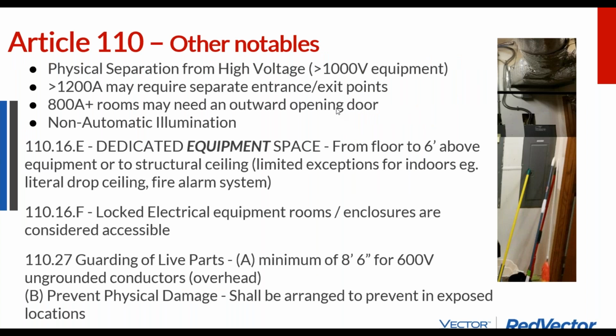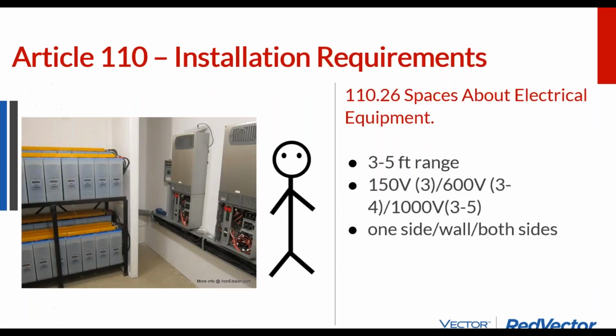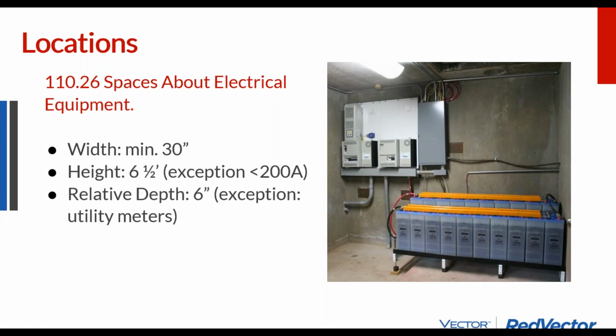And so, if you're planning your batteries, and if you're using batteries that need maintenance, what that means is at minimum, if there's nothing else around, you need a 3-foot walkway on all sides of those batteries. And if there is electrical equipment around, depending on the voltage of that battery bank, you're looking at a 4-foot walkway, or if it's a high voltage battery bank, you might be looking at a 5-foot walkway all the way around the battery shelf.